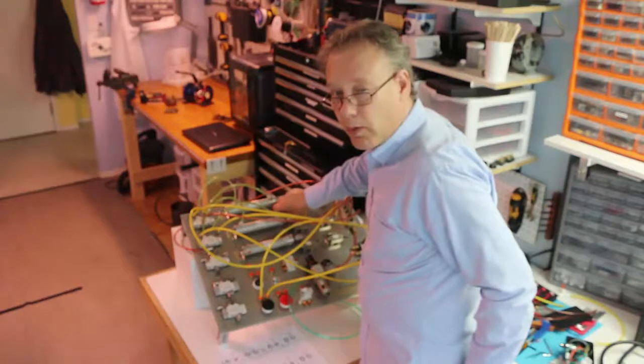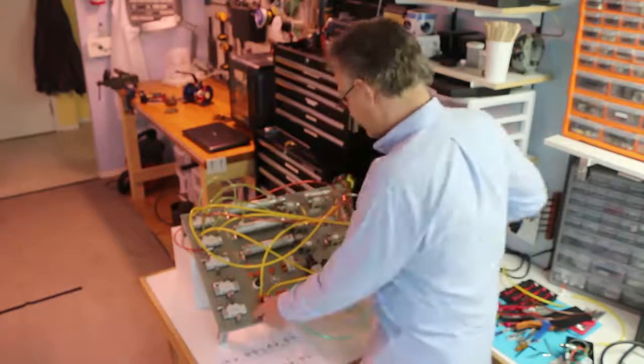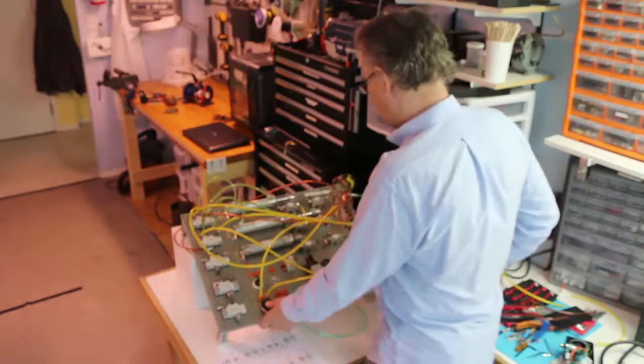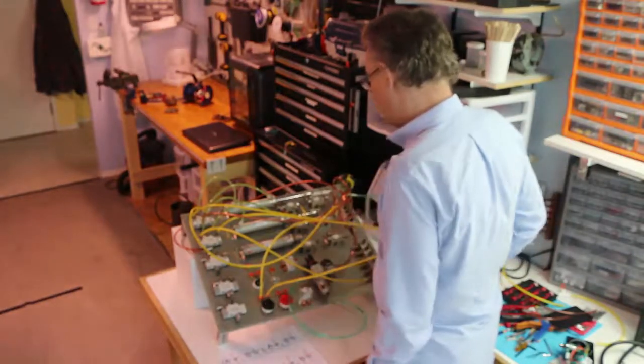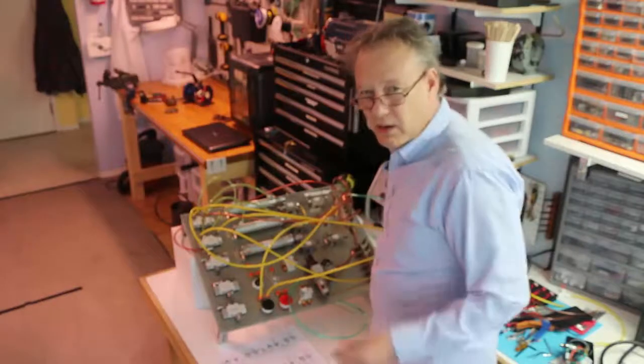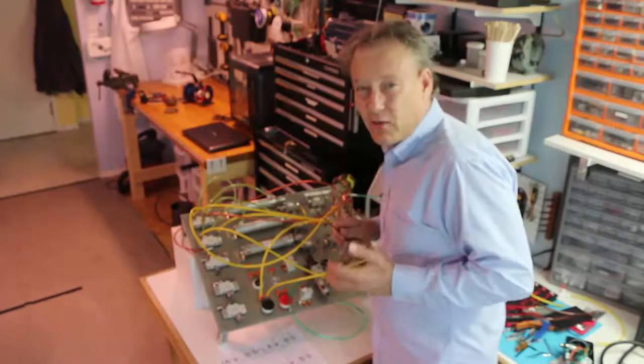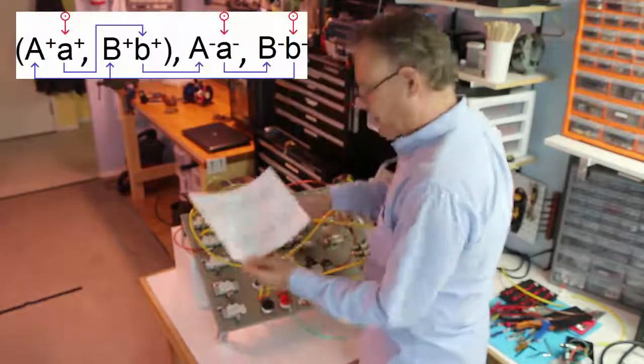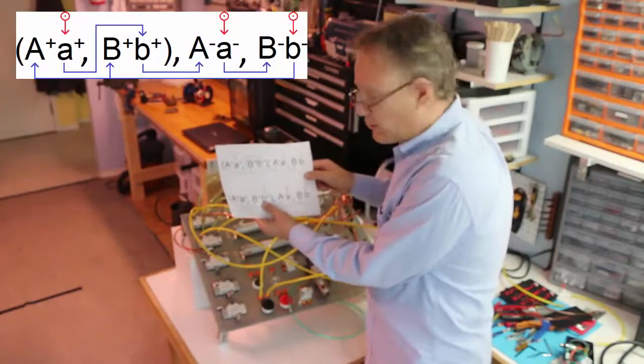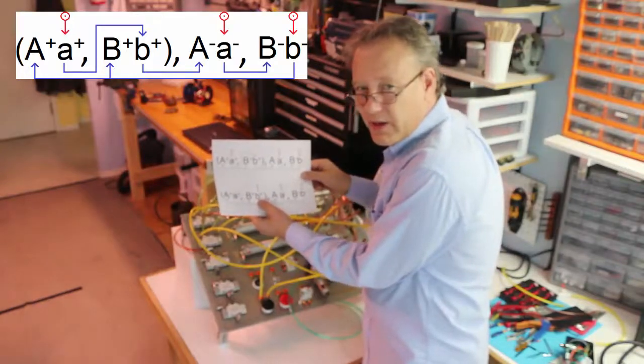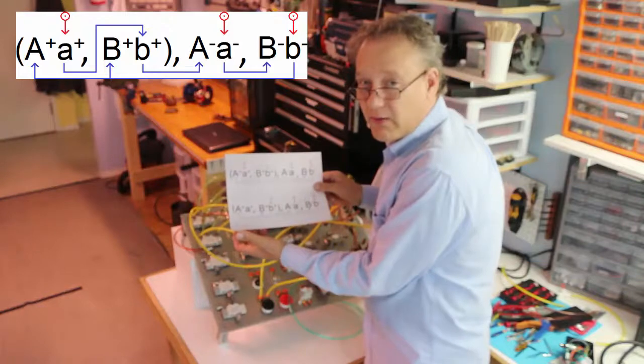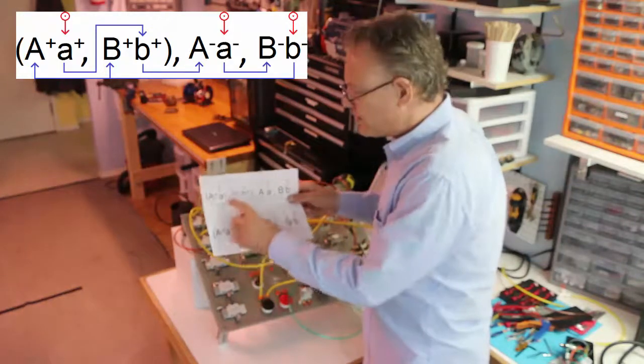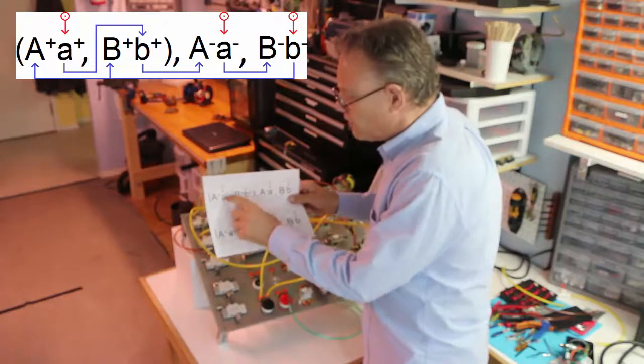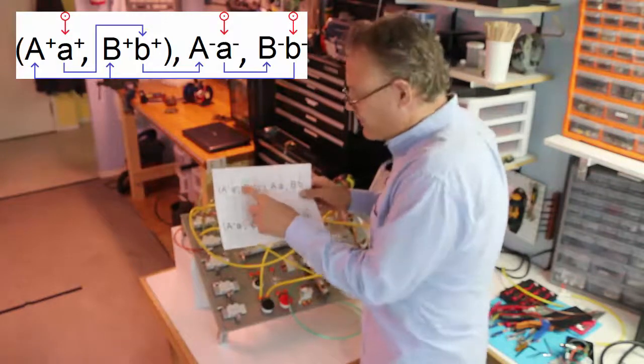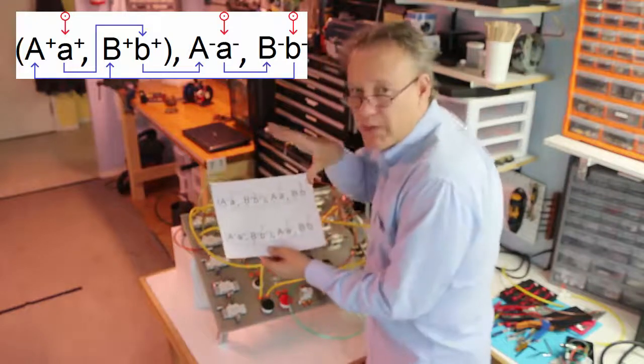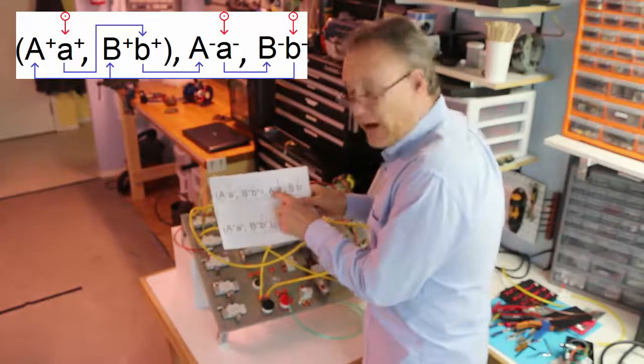Let's say that A was actually really quick and B was the slow poke. Let's see what happens then. So it's actually okay if A gets out really quickly because it's waiting for B anyway. But if B gets out first, then as we can see, A never actually goes out all the way. So it's important that we do an AND with our limit valves, in that this one and that one both have to be passing for this to finally happen.